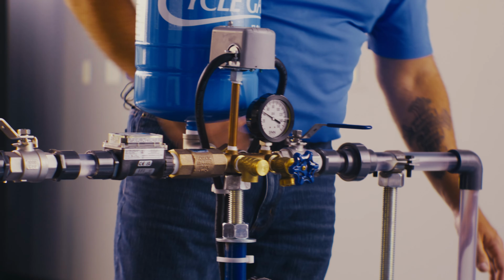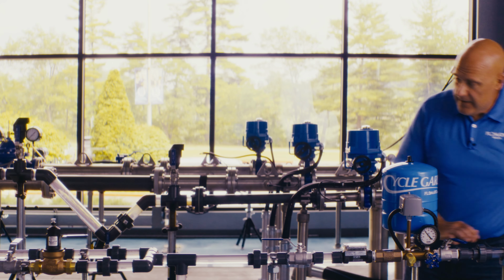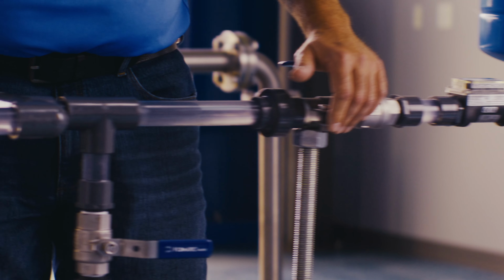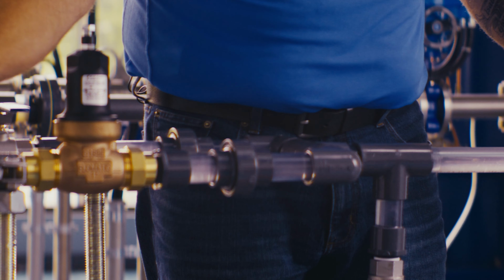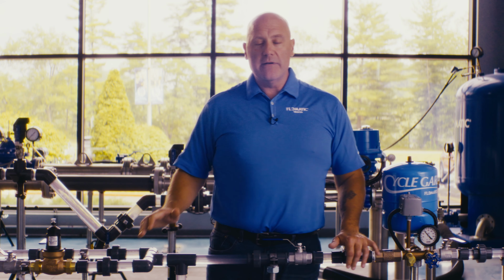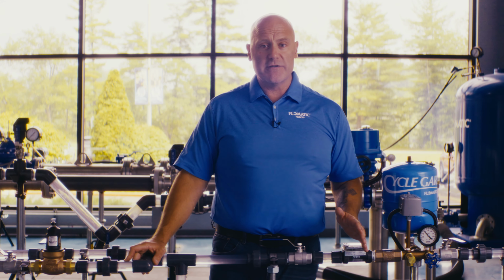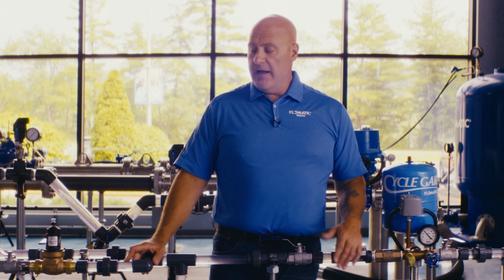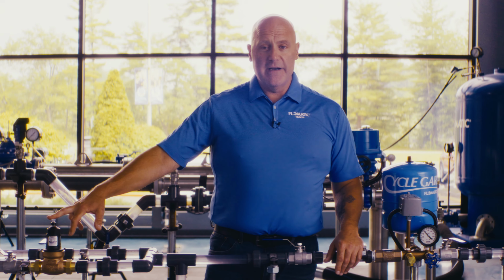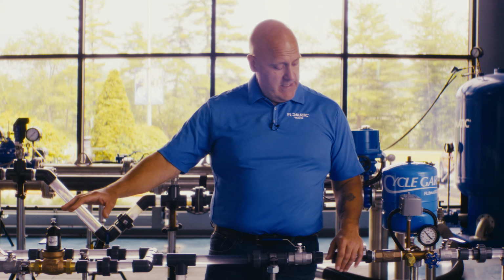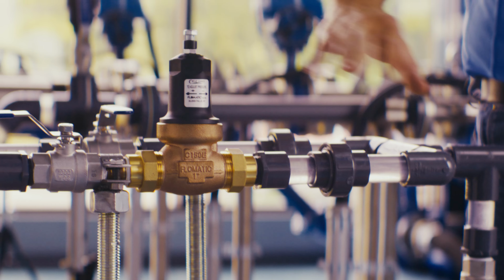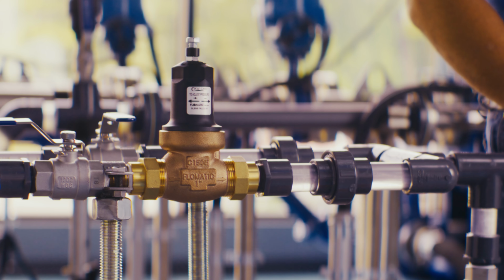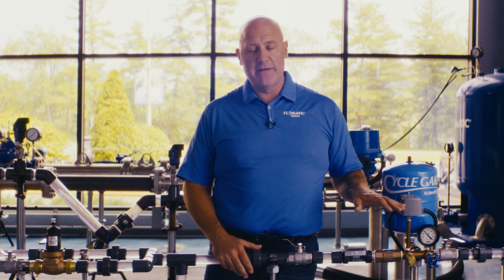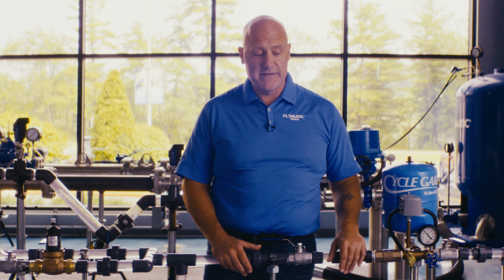One way of doing that is with a Cycle Gard. When this builds up to 60, I'm going to shut the valve off. And now I'm going to switch over to our first Cycle Gard unit. Now what's going to happen this time around, pressure is going to drop to the 40 PSI setting of our switch. The pump is going to kick on, and this Cycle Gard is set for 50 PSI. Once the pressure at the Cycle Gard hits 50, that's all that Cycle Gard is going to let through it. So our system is going to stay constant at 50 PSI as long as there is demand on the system.